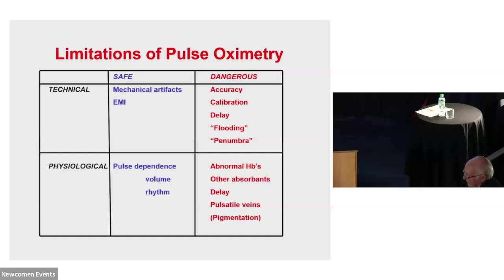They can be affected by flooding, which is bright light shining underneath them. Penumbra is when the two light-emitting diodes are seen through two different thicknesses because they're not close enough together. The flooding one is interesting in that it can be flooded by too much light, or even worse, Draeger make a small operating lamp, which is used an awful lot, which is LED. If you turn the LED down, you realise that it's not just dimming it down like you would with an ordinary incandescent bulb. It's flashing, and you can't see it's flashing, and it will interfere with the signal. So they recommend, especially with neonates, that they put a piece of material over the hand to black out these very bright LED lamps.